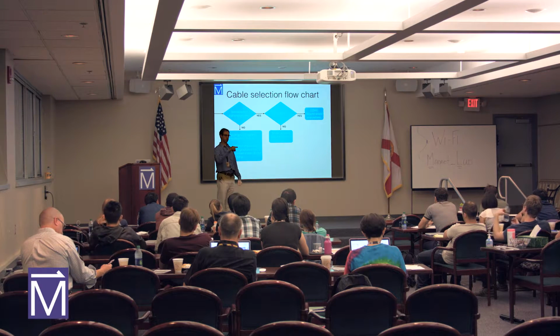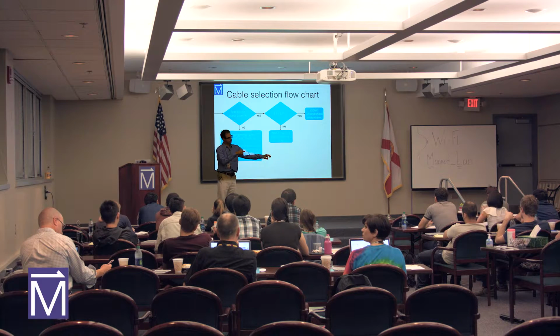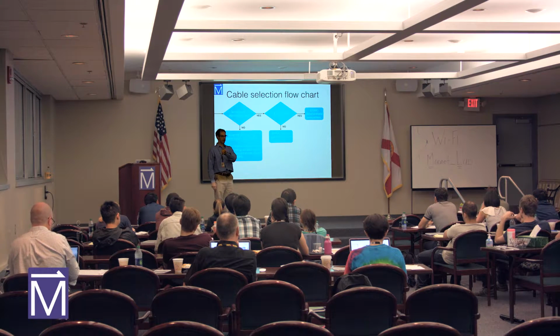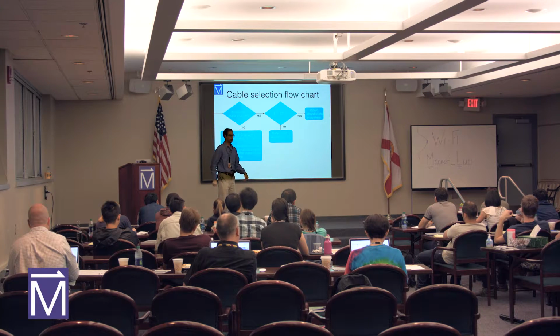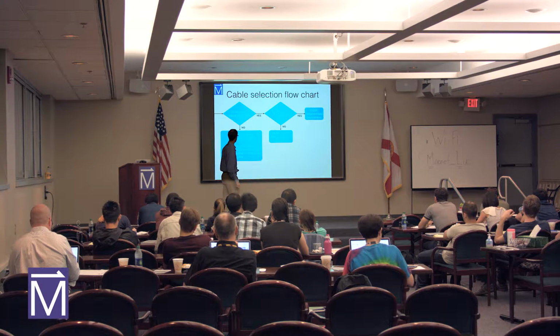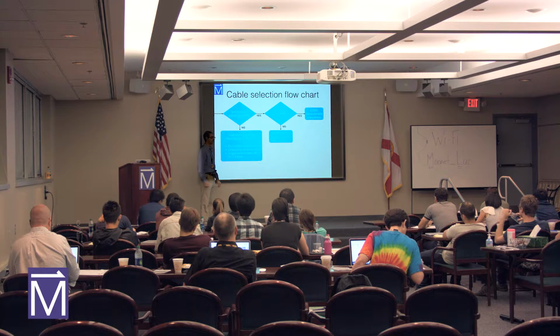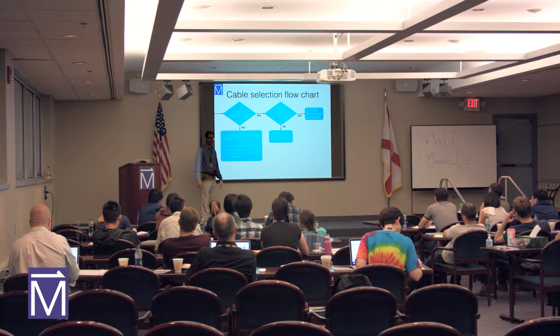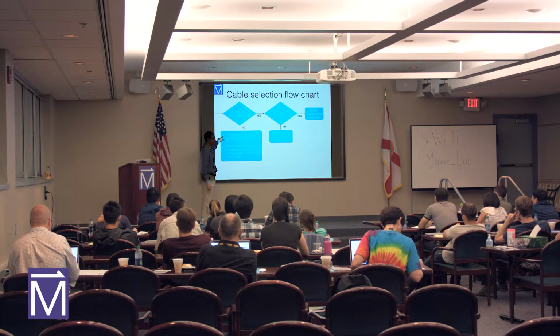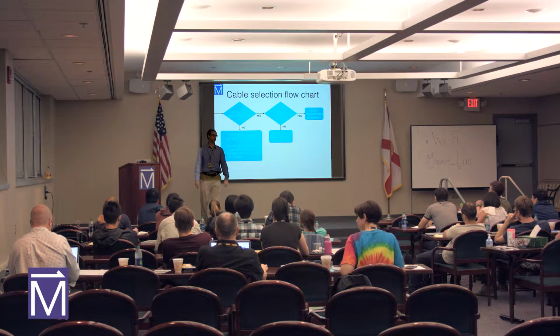So you have the core, which is your signal one way. You have the sheath returning the other way. And then you have a separate shield around all of that. So you're keeping the interference on the shield and off the return. The situation we live in most of the time here, because we don't want to deal with ground loops and such things, is twisted pair with differential inputs.